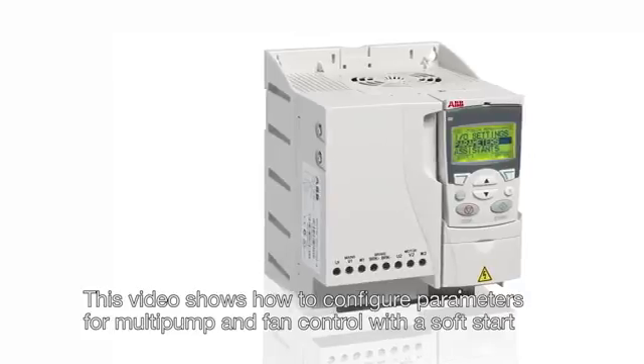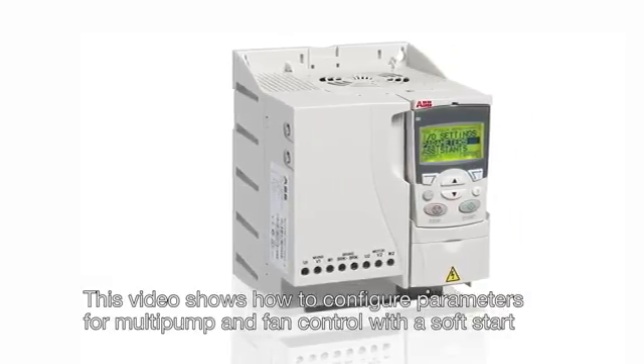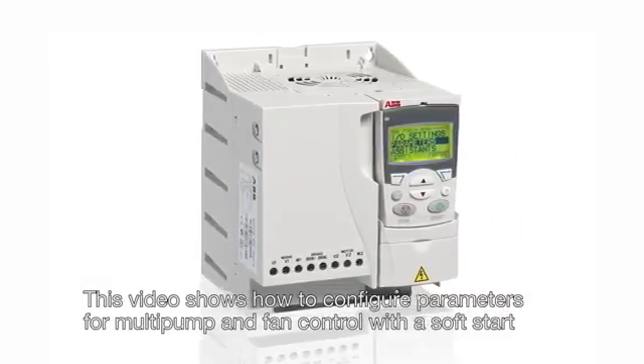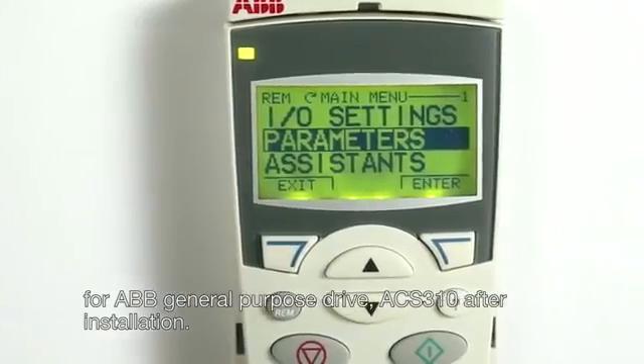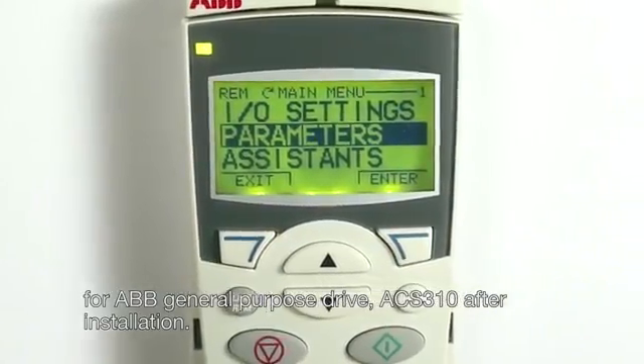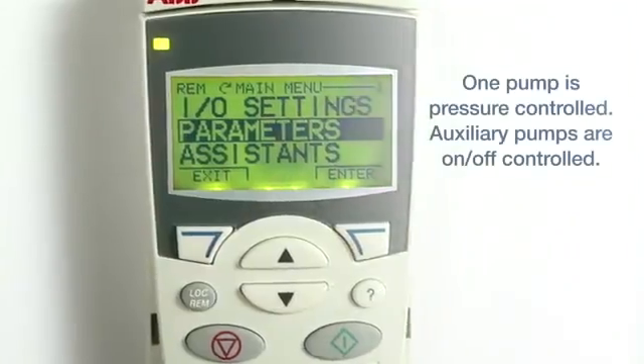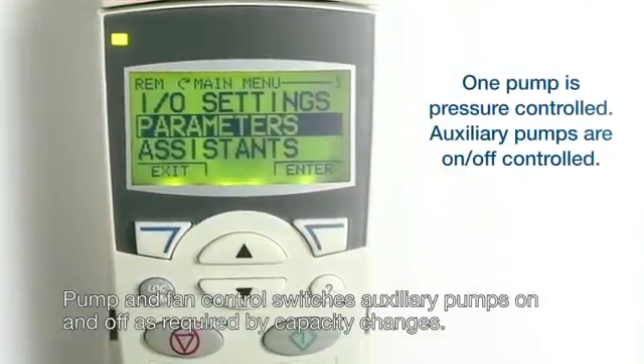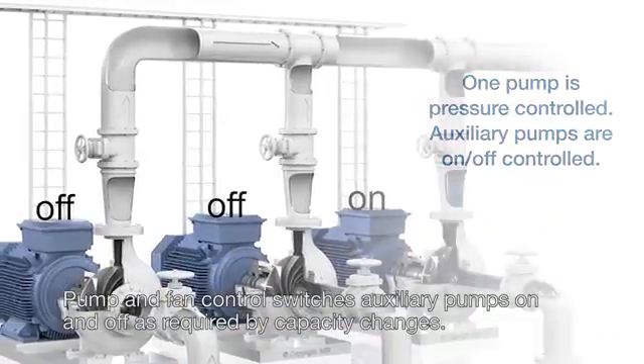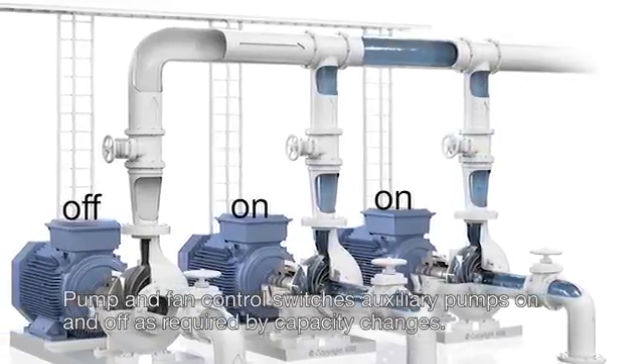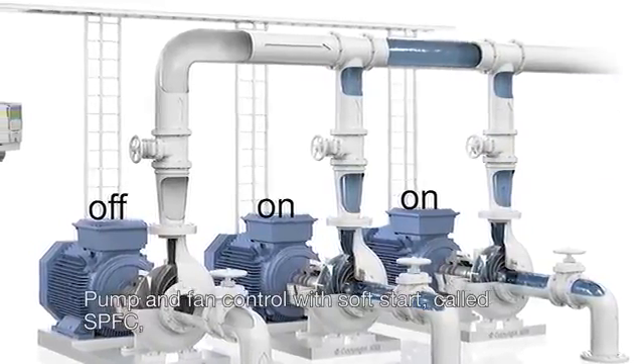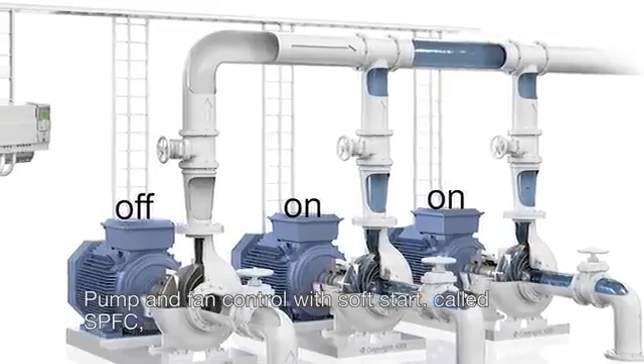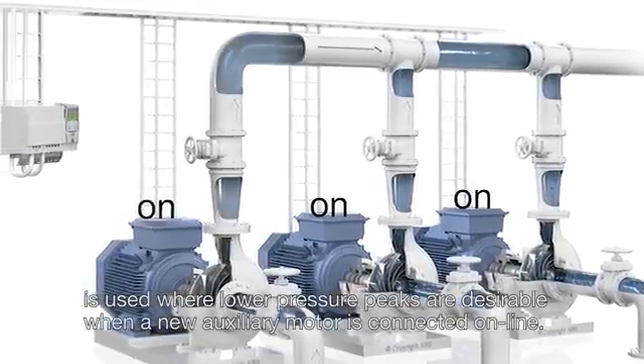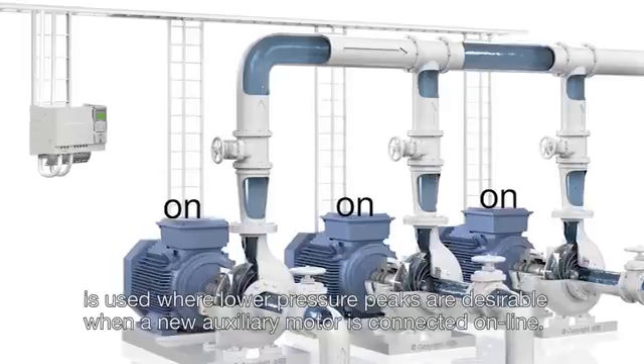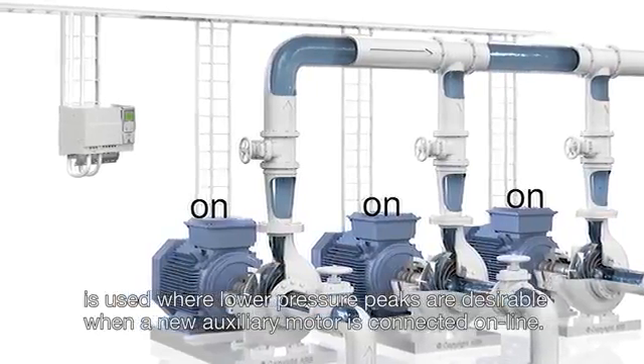This video shows how to configure parameters for multi-pump and fan control with a soft start for ABB General Purpose Drive ACS310 after installation. Pump and fan control switches auxiliary pumps on and off as required by capacity changes. Pump and fan control with soft start, called SPFC, is used where lower pressure peaks are desirable when a new auxiliary motor is connected online.